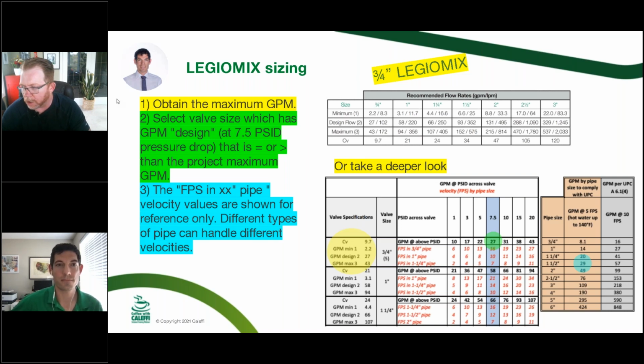I know in Toronto, there was a run of bad pipe that came back to a manufacturer offshore, right? But at the end of the day, it has to be properly sized because the biggest thing is you will get a phone call of this is not working properly. We're having issues. We're not getting hot water. And you likely will have component failures.